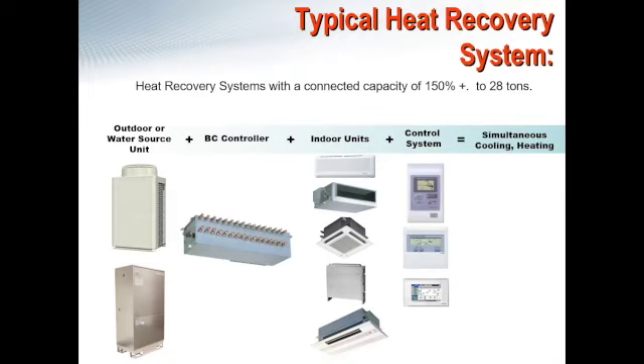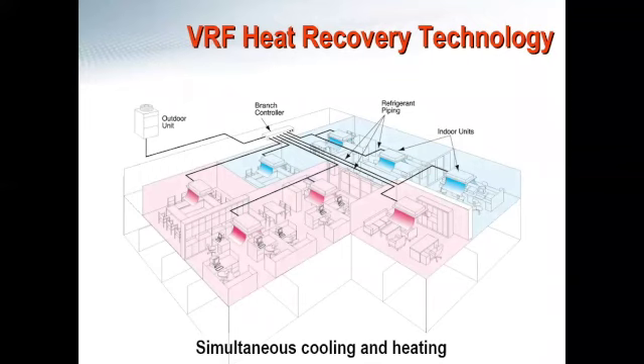But just moving along, the BC controller is what we talked about being that traffic cop. You can see all of those ports. This is our 16-port model. That's there to divert all of that refrigerant from zones in cooling to zones requiring heating. And one thing to think about in these, I'm going to take one second to go a slide backwards. Here we go. So this is showing your absolute perfect application where you're going to have a totally balanced load. If you have your 4 zones over here in cooling and 4 zones requiring heating of a similar load profile, this is going to allow that condensing unit to work at exactly 50%. This is one of the reasons that VRF technology can be so efficient, and we're going to touch on some of the compressor information in a few minutes, but this is really what's going to allow you to beat all of the new efficiency legislation that's coming out and surpass all of the competitive HVAC technologies as far as efficiency goes.